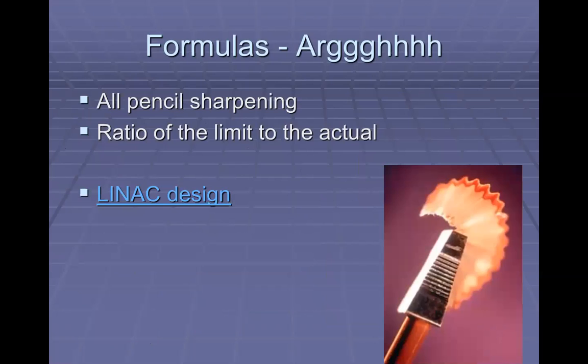So yeah, you can see that there's a lot of going through individual spaces around the vault. You have to factor in every single room that touches this LINAC vault, and then do this equation and figure out. So you want to design it conservatively, but then you also have conflicting interests of hospital administration saying, hey, lead's expensive.